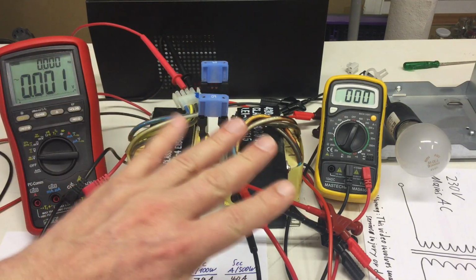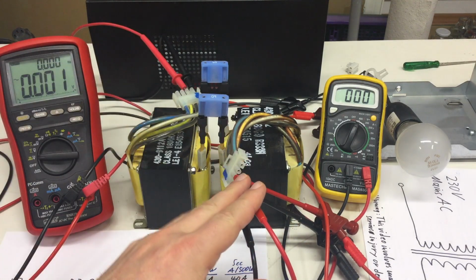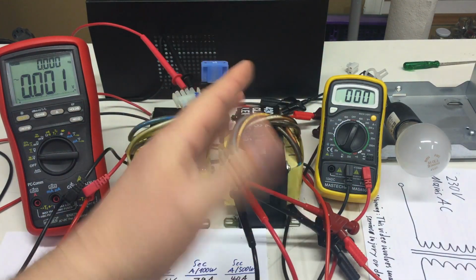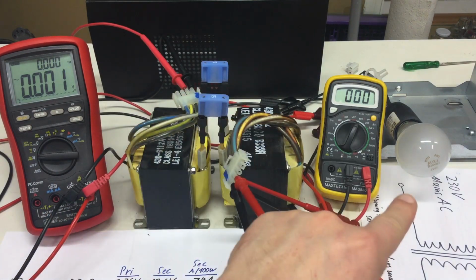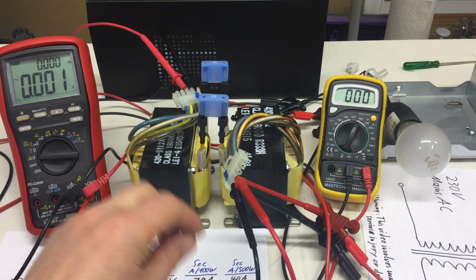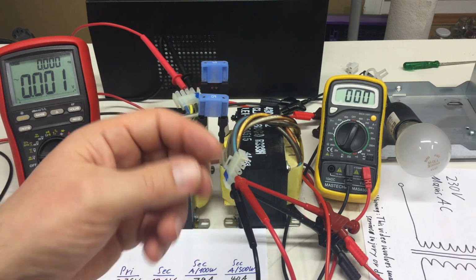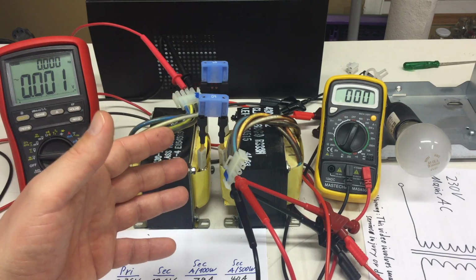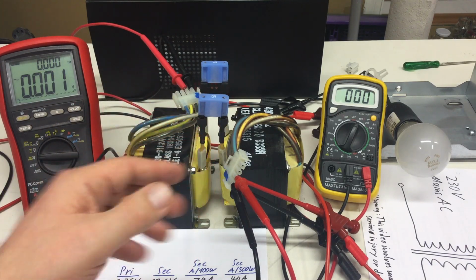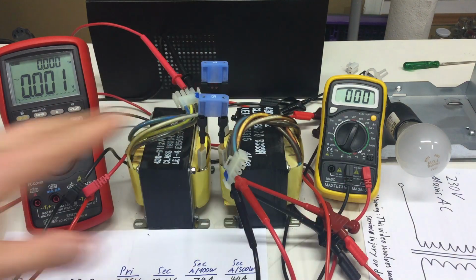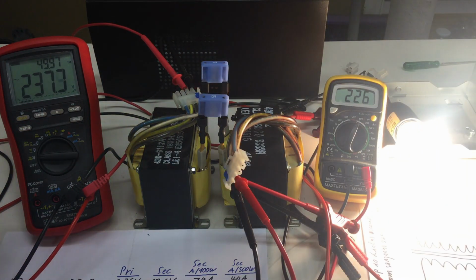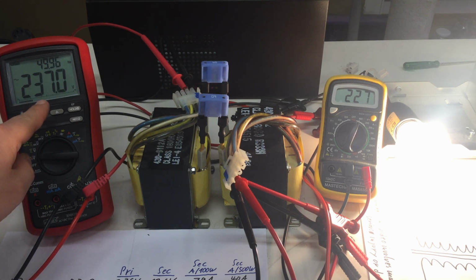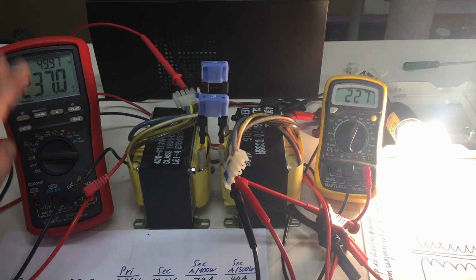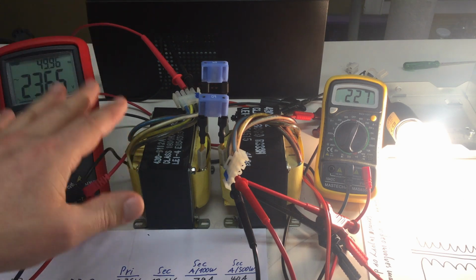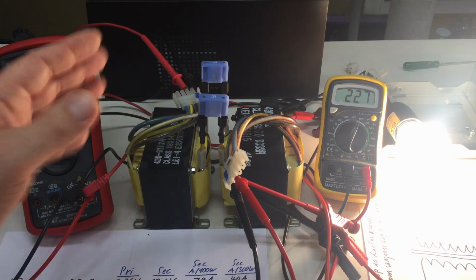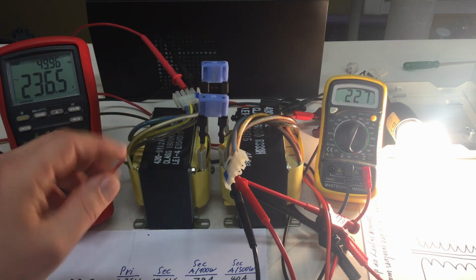So basically, whatever tap I used, I had a voltage drop of about 7 volts for the 100 watt load. For 500 watts, that would mean a voltage drop of 35 volts. And then, with what we have here, 237 minus 35 is 202 volts, which is below the minimum voltage allowed for mains AC, which is 207 volts.